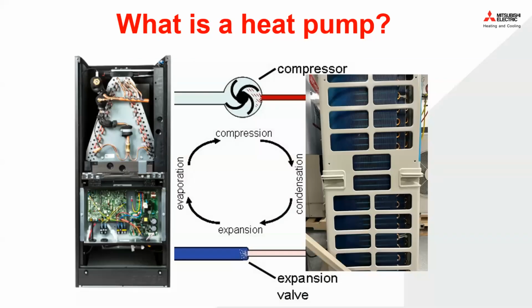So here are some rudimentary images of the components of a heat pump system. We have a compressor, an expansion valve, an evaporator and a condenser. Now the evaporator and condenser can be exchanged because we have a reversing valve that allows the system to both heat and cool. So at one point, one side could be capturing heat and the other side discharging, and then vice versa. Now your compressor doubles as a pump, but its main function is to increase the pressure. And then the expansion valve, as its name suggests, lets the refrigerant expand and reduces the pressure.